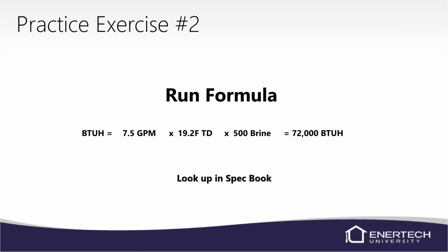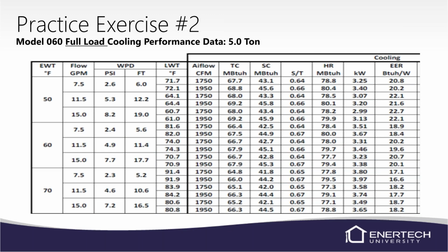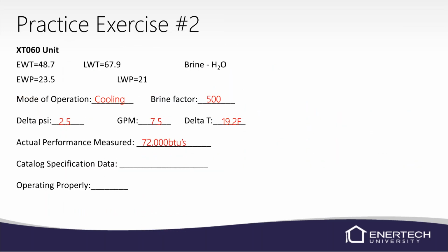Again, that's just a number. We'll have to look it up in the spec manual. Again, 50 degree entering water temperature, 7.5 GPM, 1950 CFM. So that tells us 80, actually it's supposed to be 80,400. I think when I adjusted these to the lengths, it kind of threw that off a little bit. I apologize. So it should be 80,400 BTUs, 1950 CFM at 7.5 GPM. So we know that number now. We actually measured 72,000. The catalog was at 80,400 BTUs.